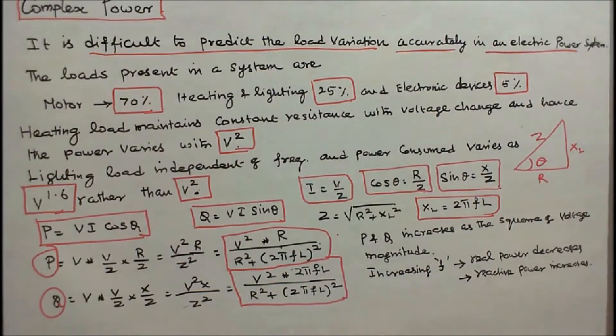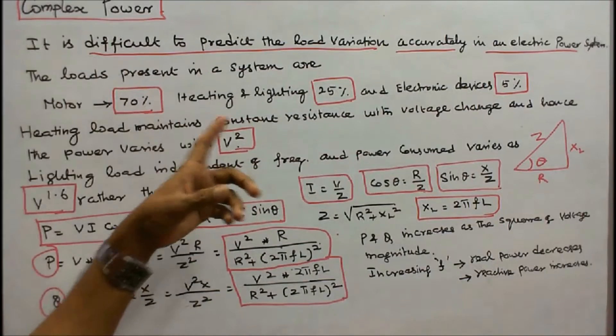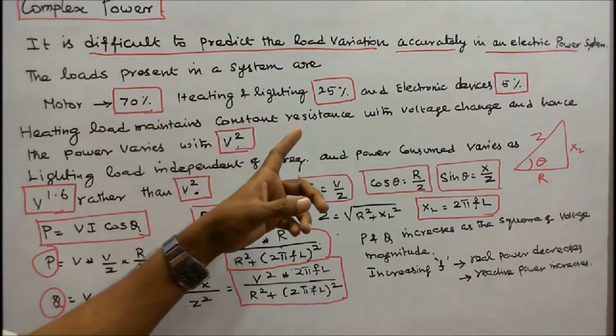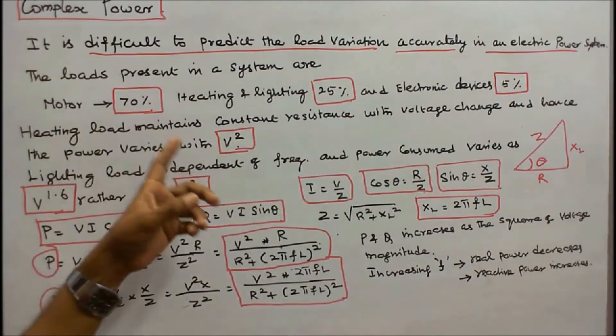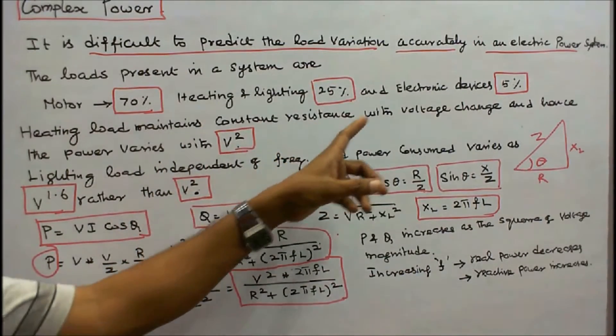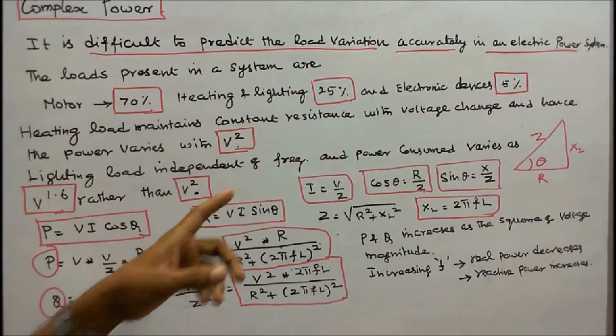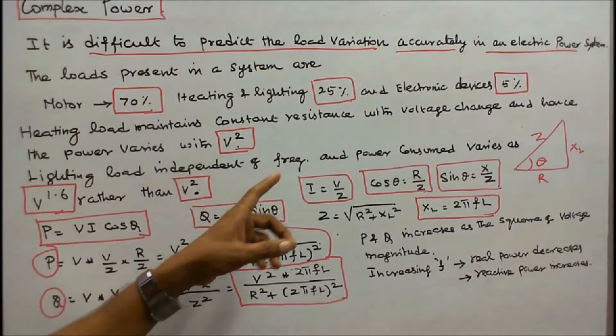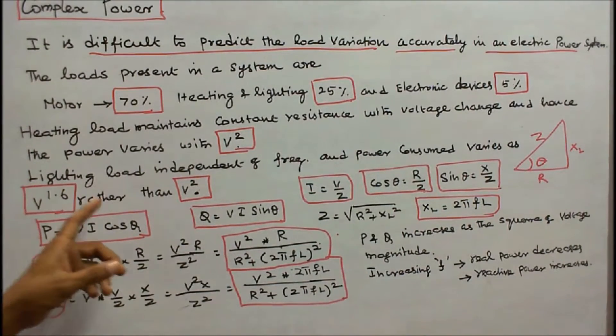It is difficult to predict load variation accurately in an electric power system. The loads present in a system are: motors 70%, heating and lighting 25%, and electronic devices 5%. Heating load maintains constant resistance with voltage change, so power varies as voltage squared. Lighting load is independent of frequency and power consumed varies as V to the power of 1.6 rather than V squared.